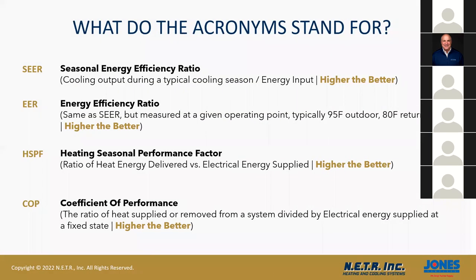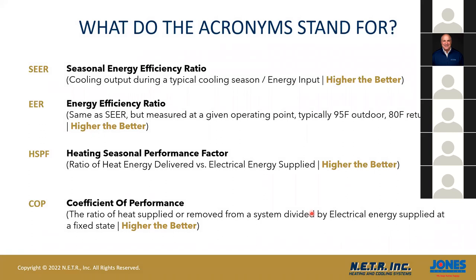Oh, I'm sorry. Let me go back to the slide. The energy efficiency ratio. This is what's called the EER. All right. It's the same as SEER, but measured at a given operating point, typically around 95 degrees outdoors and 80 degrees return air temperature coming into the room. Again, for EER numbers, the higher the better. These are acronyms that you need to know when you're looking at things.